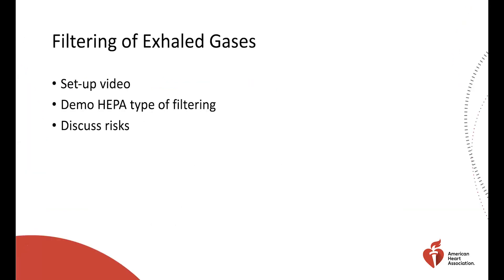When it comes to filtering of exhaled gases, we have a couple of videos for you to look at and understand. These filters allow you to filter exhaled gases, but they're not maintenance-free — they need to be changed every 24 hours. If you're administering aerosols through them, you may have to change them much more frequently.